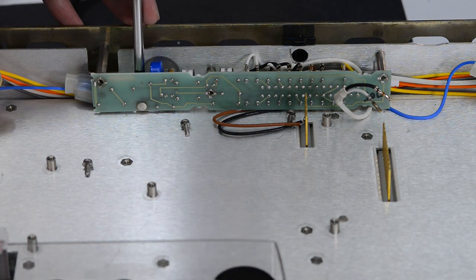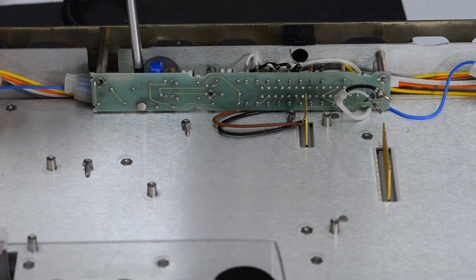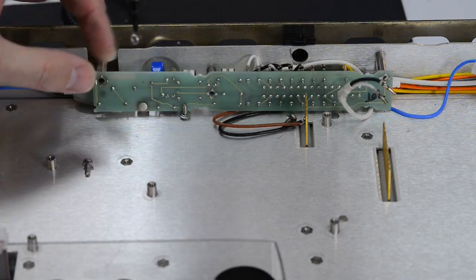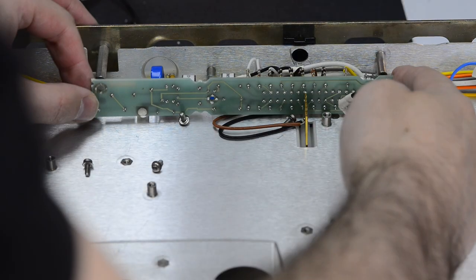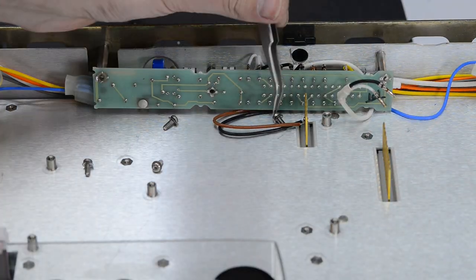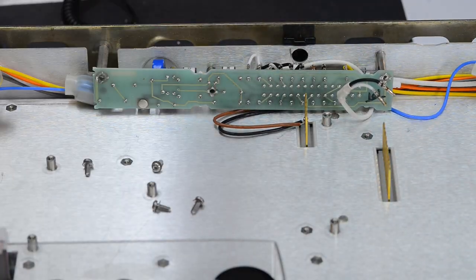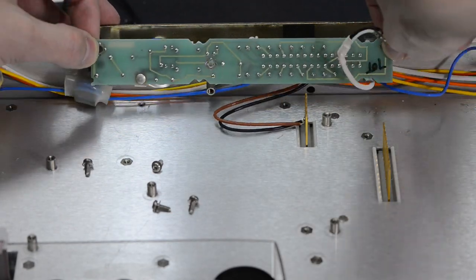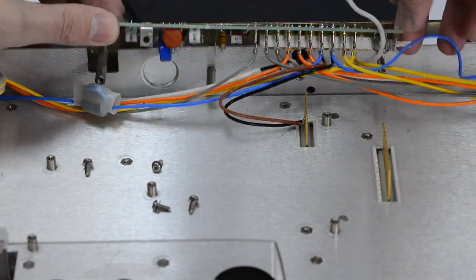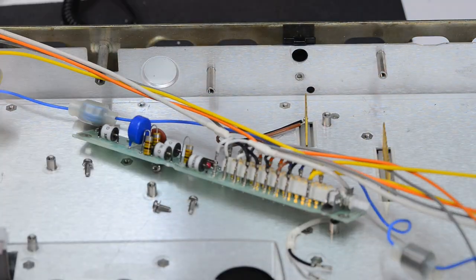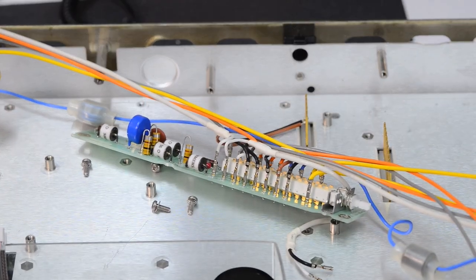It is held in place with four Torx screws. They are actually M3 screws, which is quite interesting given the instrument was designed by an American company. And now we can wiggle the board and remove the excess wires before we can plug in the terminal block from another A10.